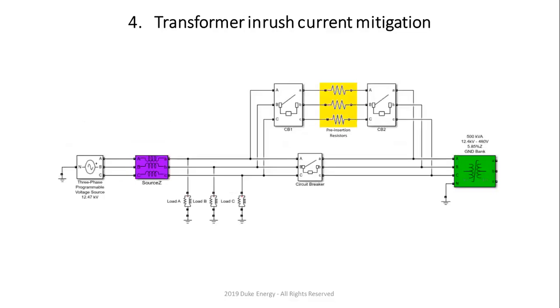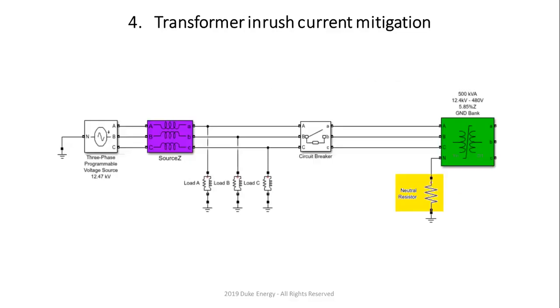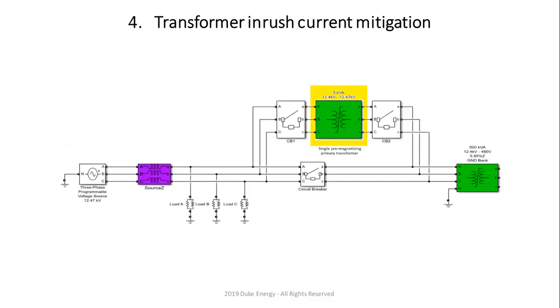The second thing I simulated is, what if we have 2 circuit breakers and put pre-insertion resistors? What kind of results do we get if we use that? The goal was to find 2 or 3 things that might work and then implement them. The third one is, what do we do if we put in a neutral resistor? This is something that happens all the time, but you don't want to do it, because when you have an islanding condition it will help with inrush current, but it is not going to help when you have a fault, because this neutral resistor will actually reduce the amount of available fault current. Also, if you ever have a delta-Y grounded transformer and try to do the inrush into the delta side, you can't do it because there's no place to put the neutral resistor.